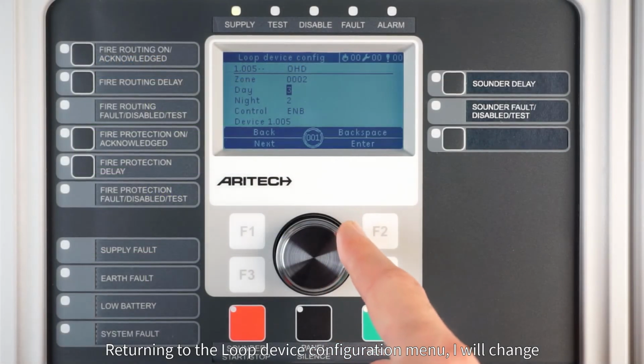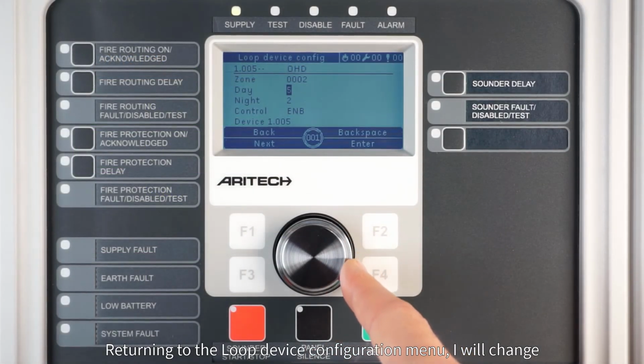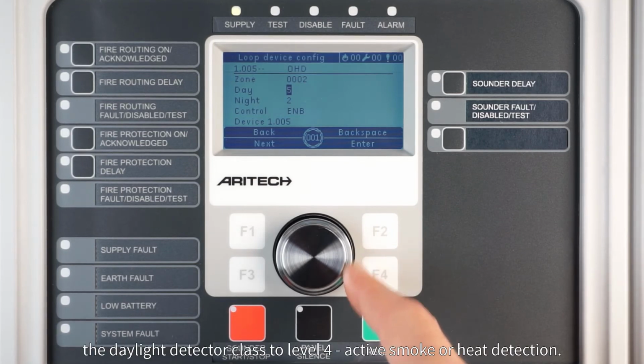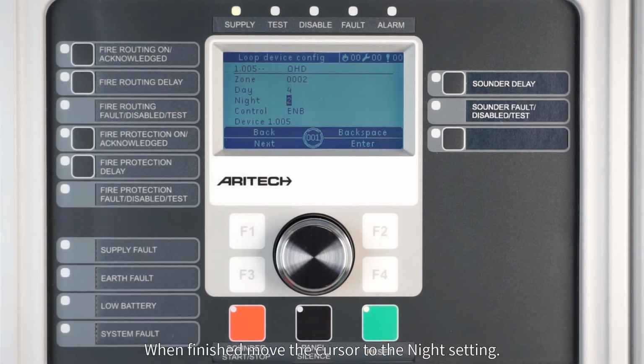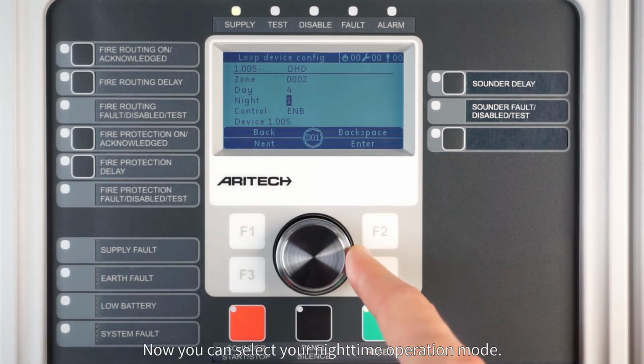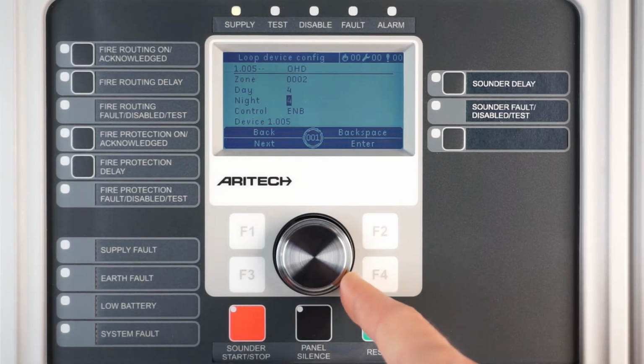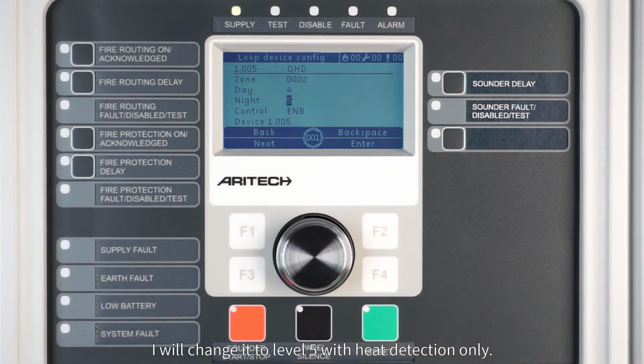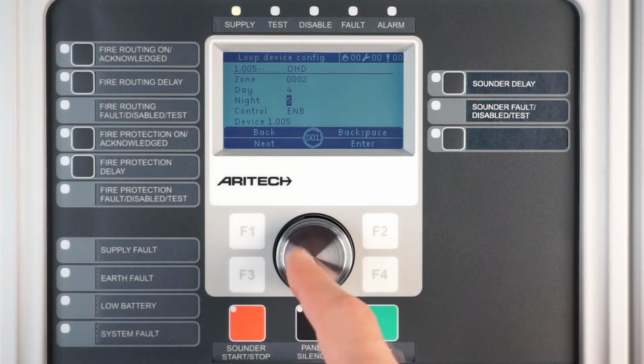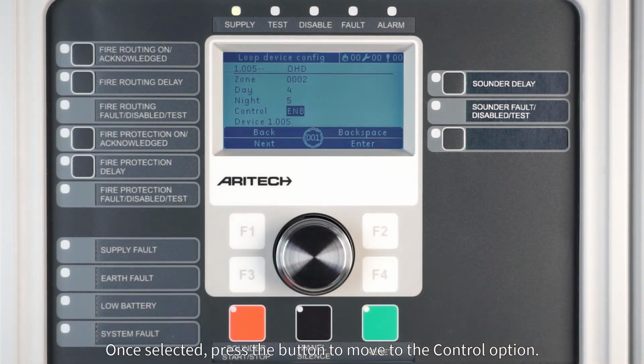Returning to the loop device configuration menu, I will change the daylight detector class to level 4, active smoke or heat detection. When finished, move the cursor to the night setting. Now you can select your nighttime operation mode. I will change it to level 5, with heat detection only. Once selected, press the button to move to the control option.